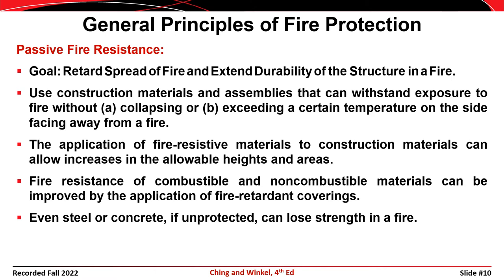The alternative to active fire resistance is passive resistance. Passive systems are designed to slow down or retard the spread of the fire or extend the durability of the structural system until the fire can be extinguished, presumably by firefighters. The time that it takes to extinguish the fire can be anywhere from 30 minutes to several hours. The amount of time that the structure has to survive before the fire is extinguished is referred to as the fire resistance rating. Typical passive resistance includes fire resistant coatings such as spray-on fire protection.